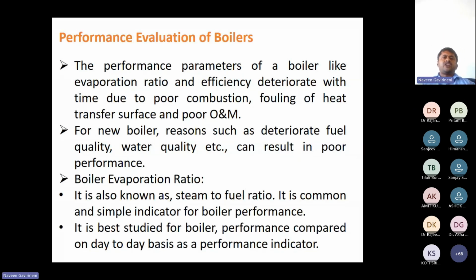We will evaluate the boiler in two ways. One is the evaporation ratio and the other is the efficiency ratio. Evaporation ratio means output by input. Output is the steam, mass of steam into enthalpy of steam, while input is mass of fuel into calorific value. So both the calorific value and the enthalpy are the same for steam, so mass of steam by mass of fuel gives the exact evaporation ratio. I will show you those values.